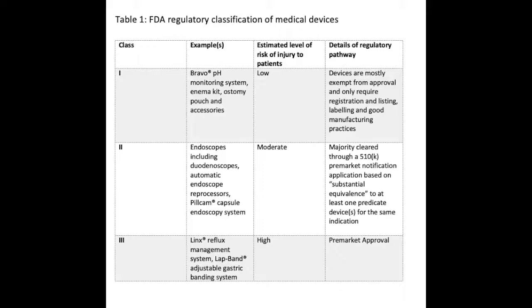Table 1 shows the FDA regulatory classification of medical devices into classes 1, 2, and 3. Class 1 devices, such as the Bravo pH monitoring system, pose the lowest risk to patients. For these, manufacturers must comply with guidelines after registering these devices with FDA. Class 2 devices, on the other hand, generally pose moderate risk to patients. Examples include duodenoscopes and automatic endoscope reprocessors used for high-level disinfection.